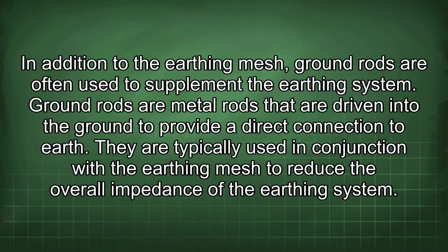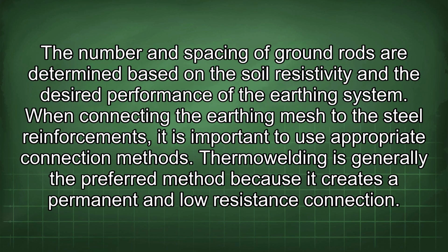In addition to the earthing mesh, ground rods are often used to supplement the earthing system. Ground rods are metal rods that are driven into the ground to provide a direct connection to earth. They are typically used in conjunction with the earthing mesh to reduce the overall impedance of the earthing system. The number and spacing of ground rods are determined based on the soil resistivity and the desired performance of the earthing system.